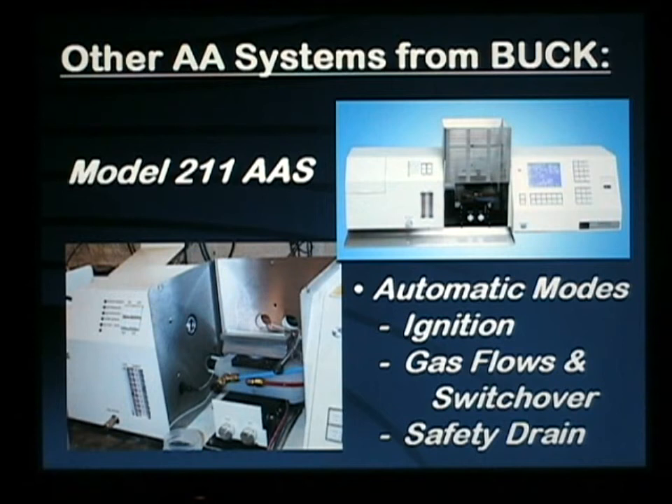Buck Scientific also offers a semi-automated AA called our model 211, which includes automatic ignition, automatic setting of gas flows and switchover from air to nitrous oxide flame, the safety drain, burner block interface, and a variety of other safety features for operations that require such control of their AA systems for insurance or safety purposes.